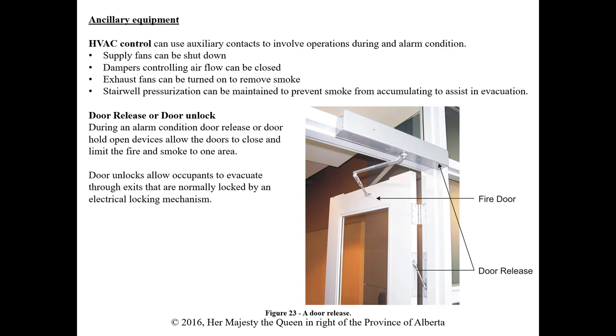Ancillary equipment can be controlled from the fire alarm control panel during an alarm condition. HVAC control uses an auxiliary contact to involve operation during an alarm: supply fans can be turned off, dampers controlling airflow can be closed, exhaust fans can be turned on to remove smoke, and stairwell pressurization can be maintained to prevent smoke from accumulating and assist in evacuation.